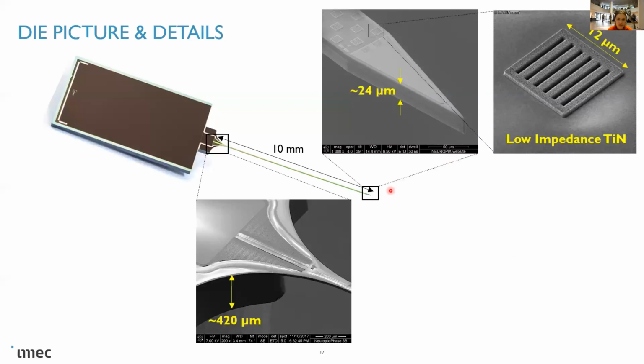So this is how a device looks when you have some close-up pictures. You have the shank that is 24 micrometers thick and this array of electrodes in a zigzag. The electrodes are 12 by 12 micrometers. They are made out of titanium nitride. This is a very low impedance electrode and also biocompatible. So it's a very good recording material.